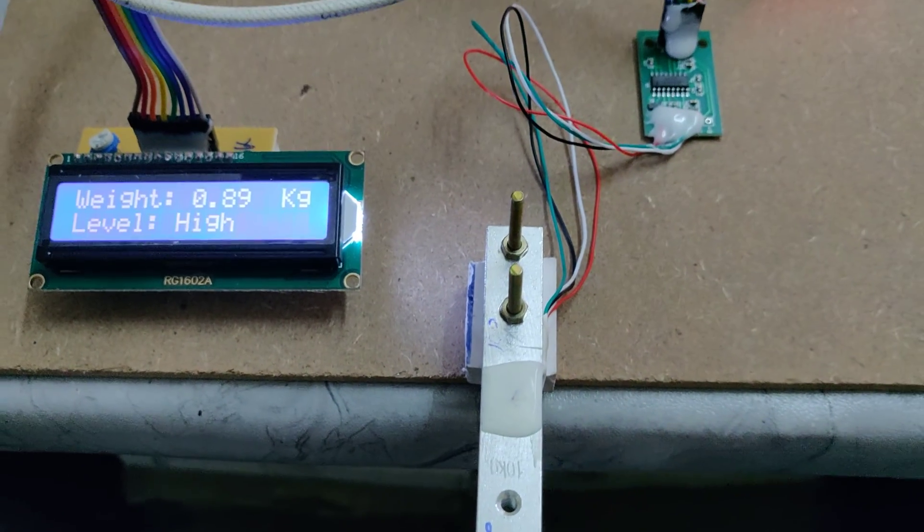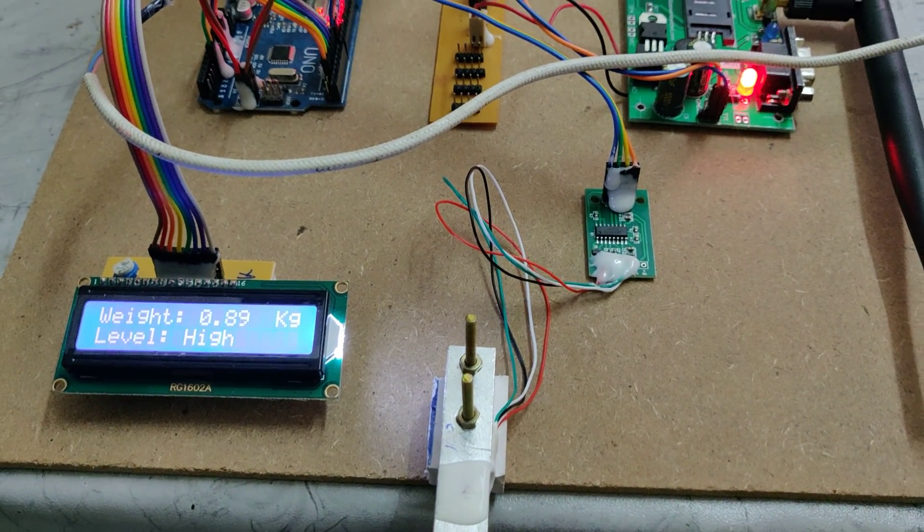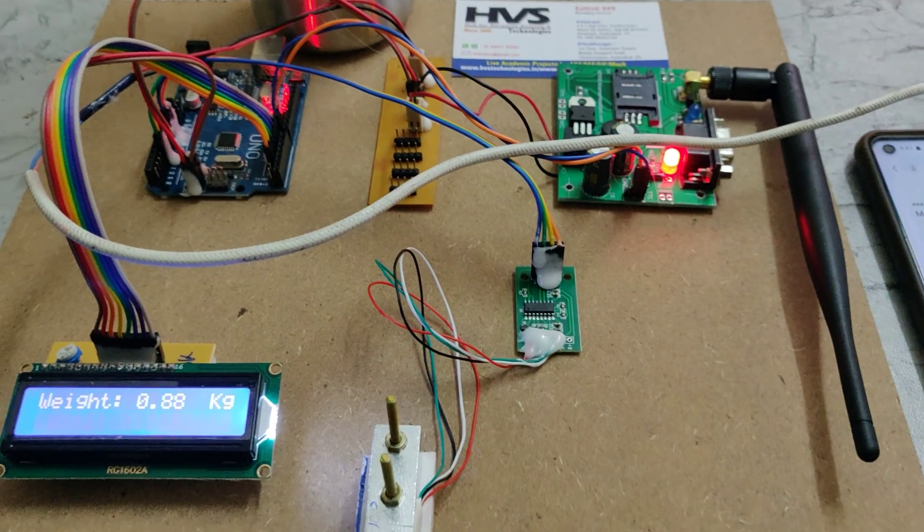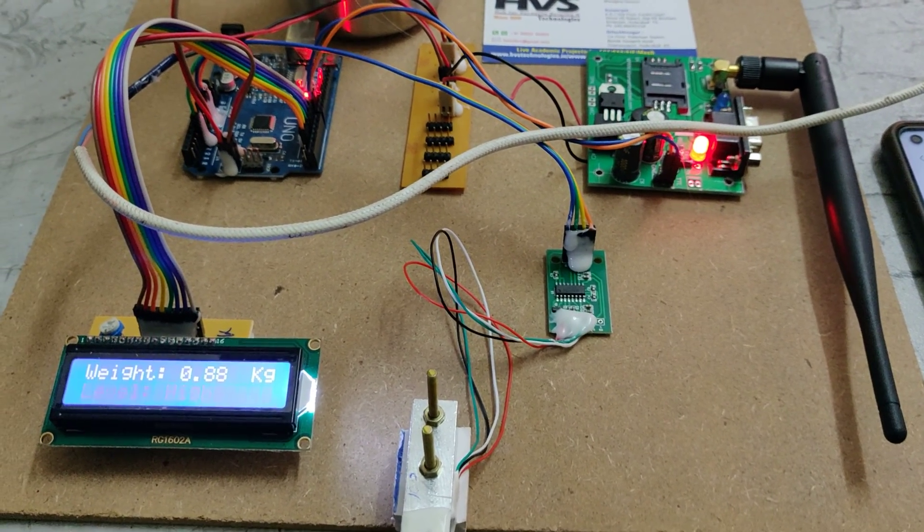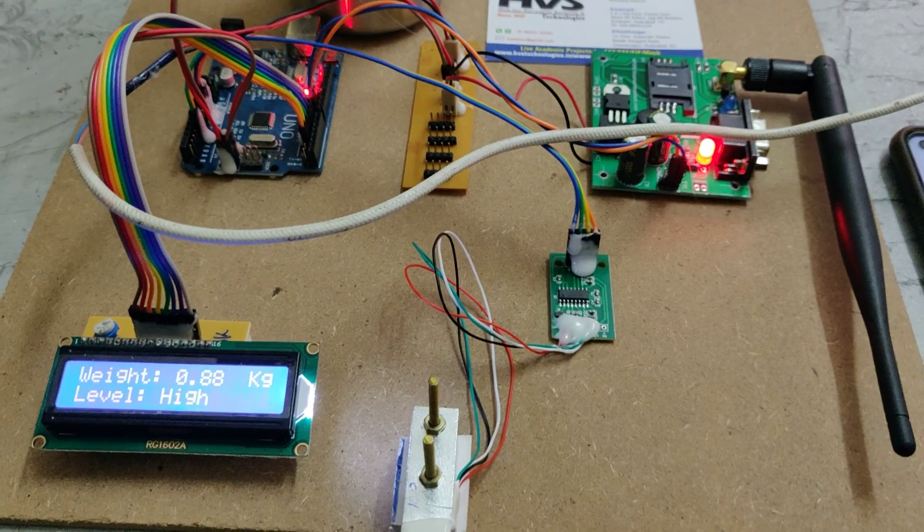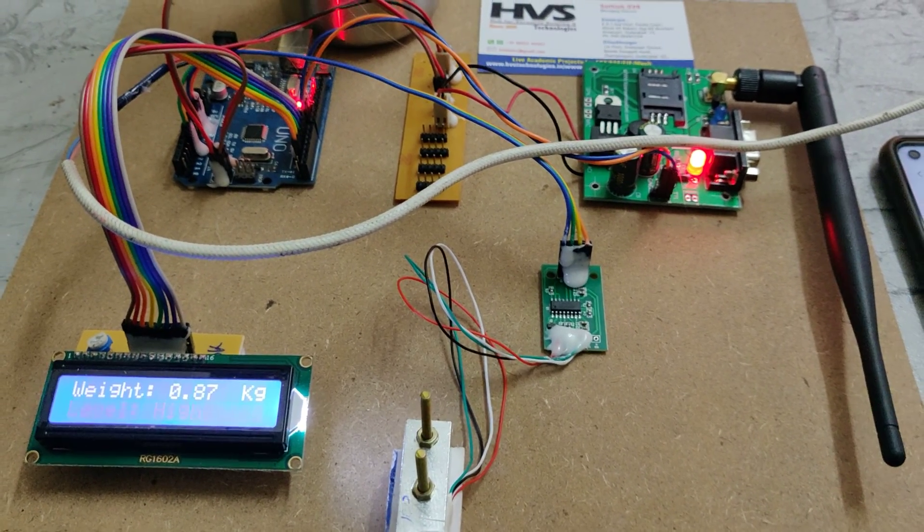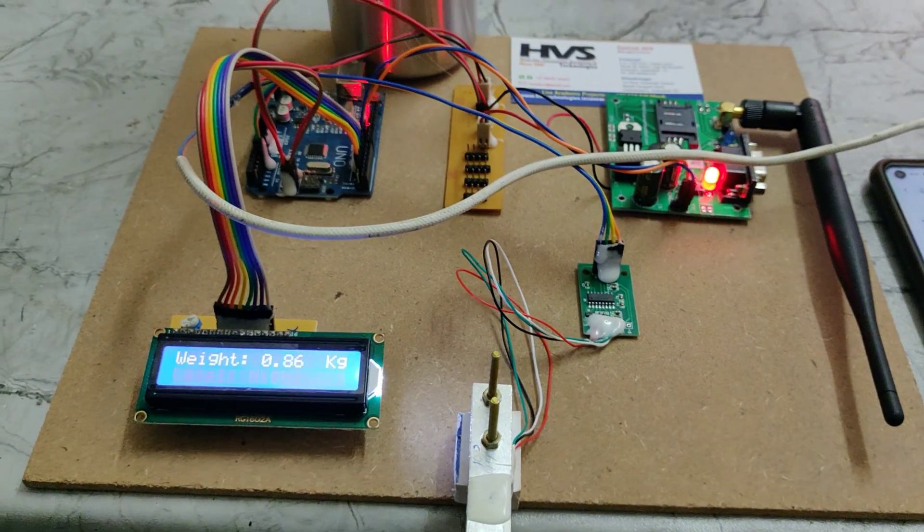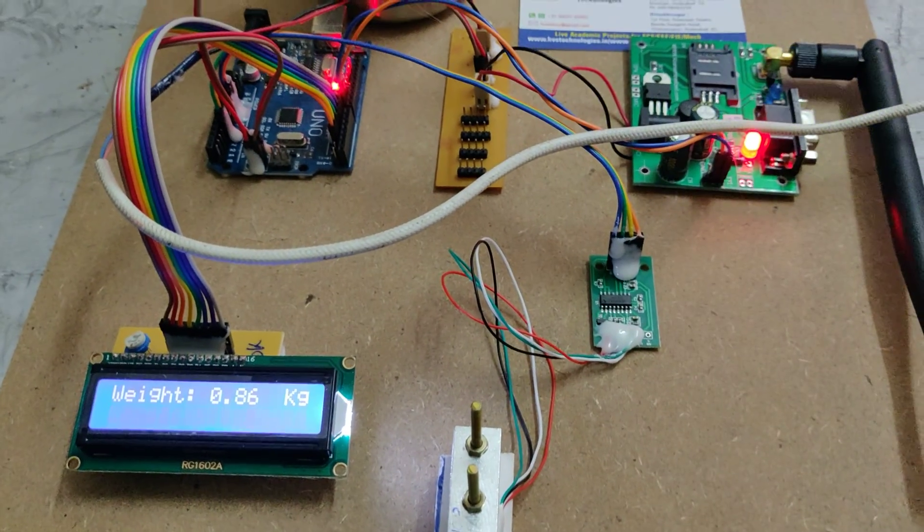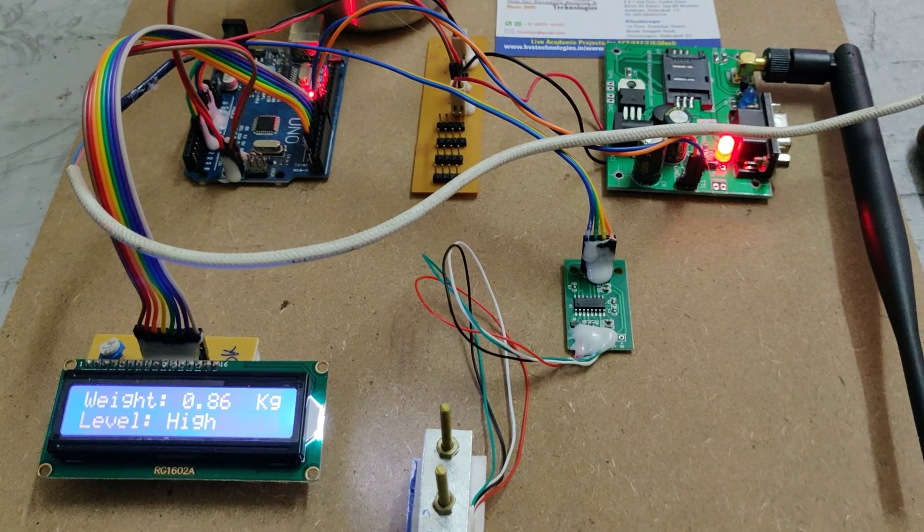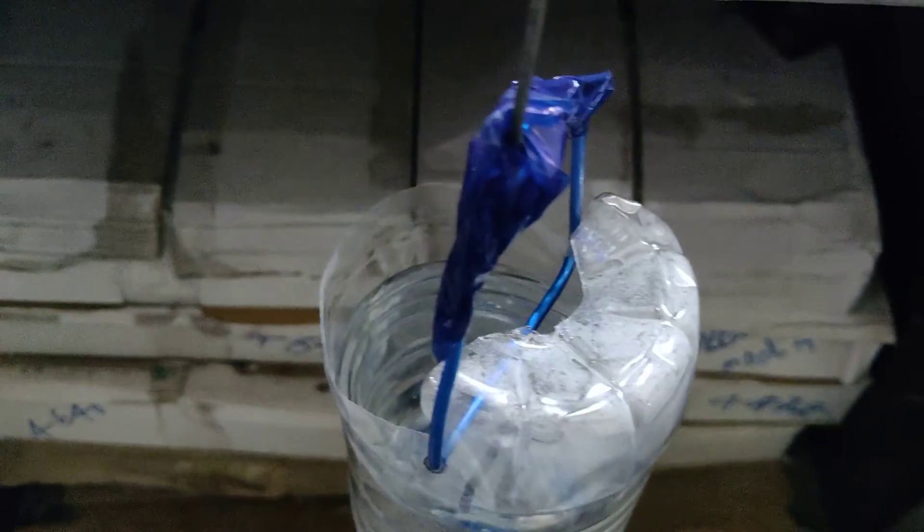Now we are releasing the water slowly. The weight is decreasing. Every 5 to 10 seconds, 0.01 kilograms, nothing but 10 grams of water, will be reduced. Around 10 milliliters of liquid is dispensing. We are keeping the saline releasing at full level. Slowly the saline level is decreasing. We can see that.